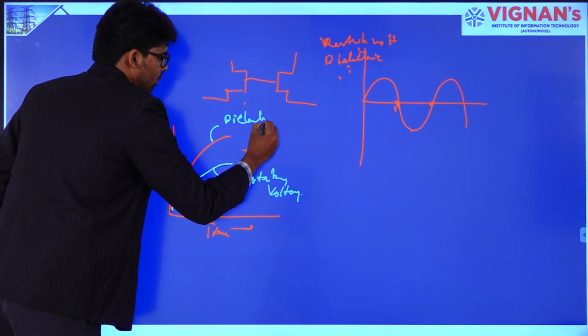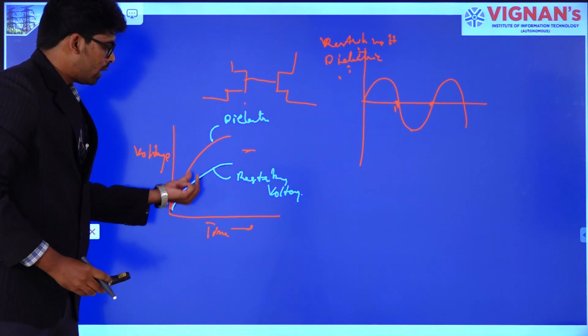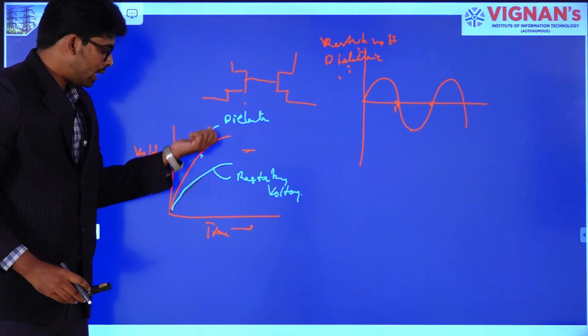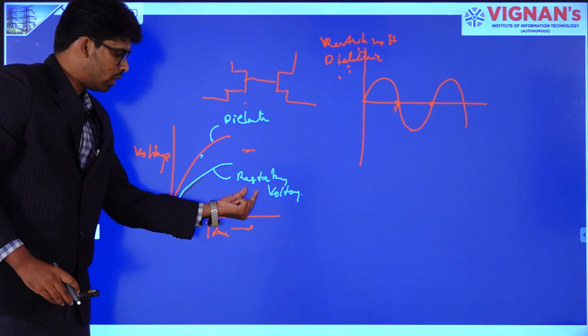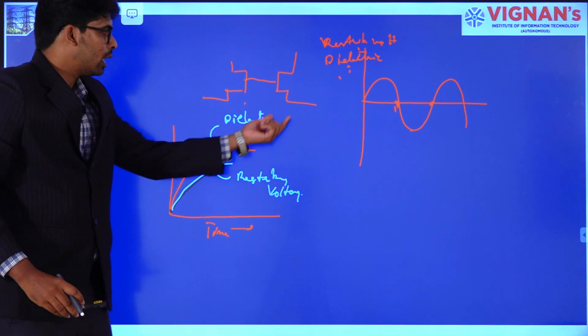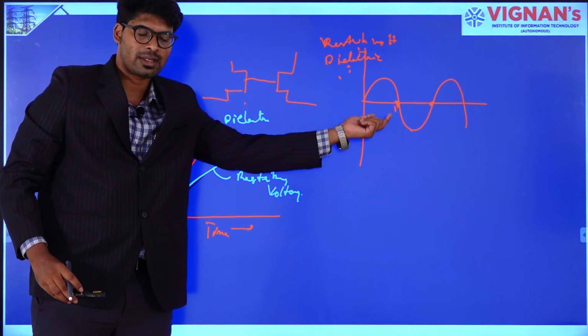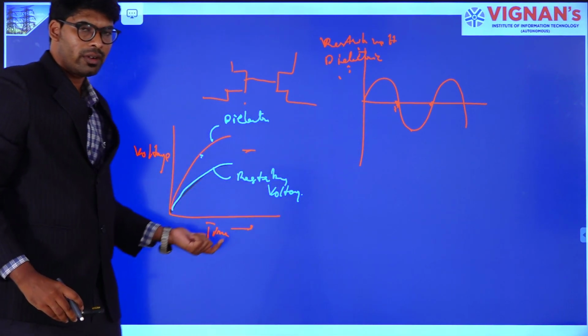If you observe carefully, if the dielectric strength is higher than the restriking voltage in due time, there will be no possibility of the arc striking again. This is about recovery rate theory.